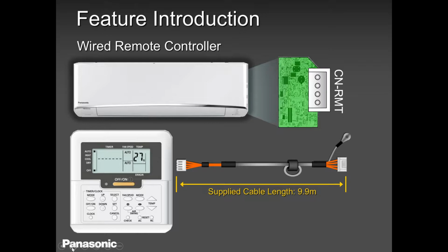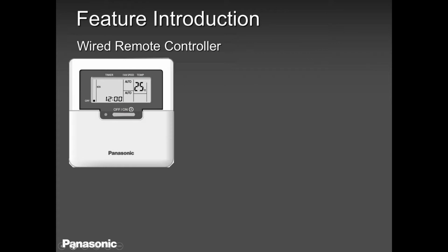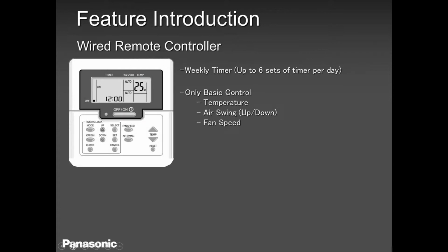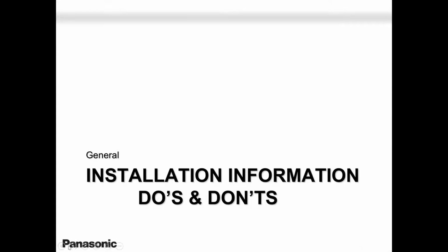It comes with a cable, 32 feet. It comes with a 32 feet cable, and if you need to extend it, you can most likely extend it with 22 gauge screen wire. Screen, maybe we can also call it shielded wire, okay? And this remote controller, just like the wireless, has the basic stuff: temperature, air swing, error code retrieving, and so forth.